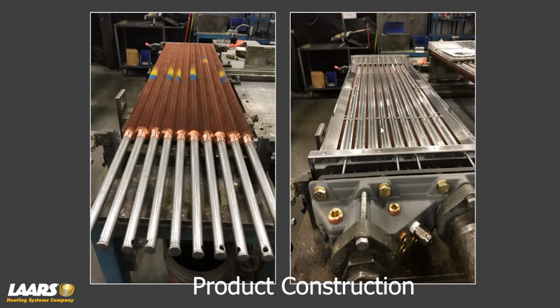Why I bring that up is if you ever have to clean a heat exchanger, you don't just want to clean the bottom of the heat exchanger. You want to take the V baffles out of position or the baffles out of position and clean the top, bottom, and in between as well.